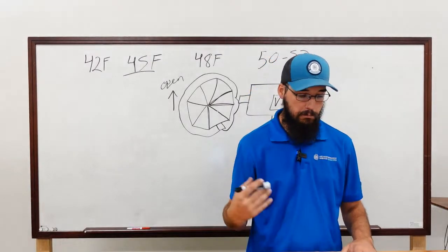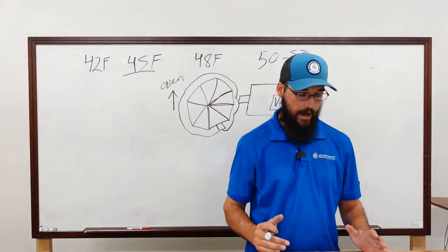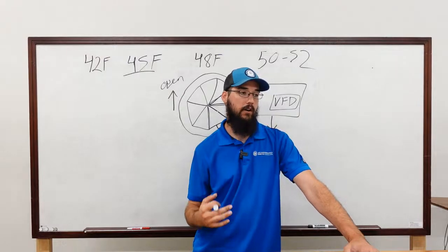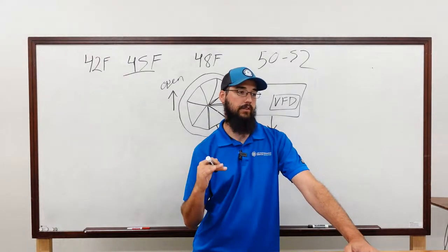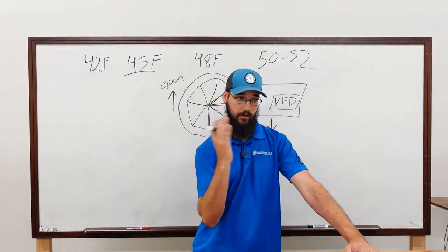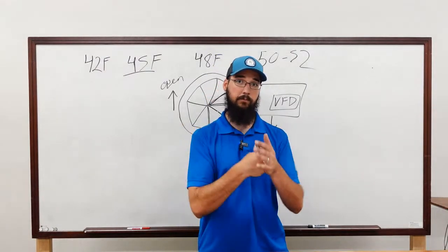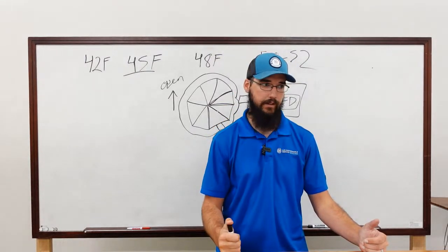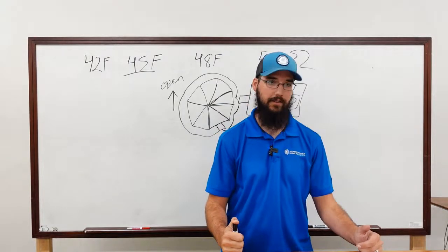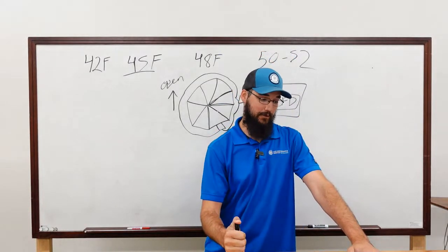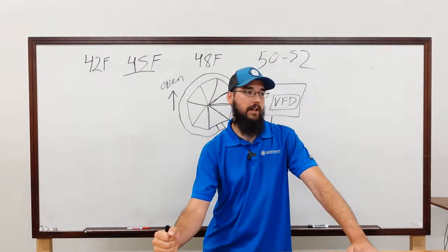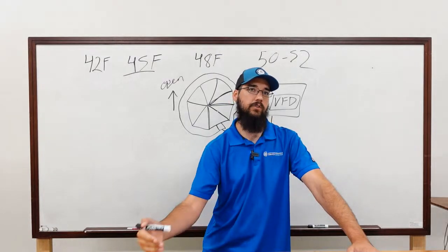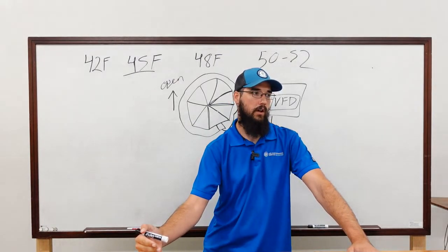Now, just to mention them, you do have three other types of starter assemblies. The other three are not variable, they're just constant, okay? So you have an XL, which is a straight across the line. It's just like a contactor on a split system, hammering shut. Now, you're not going to see that on a centrifugal. At least if one exists, I would be really interested to see the size of that thing. Send me pictures. Anyway, you would see something like an XL on a small screw machine. I've seen screws up to 100 tons run an XL start.